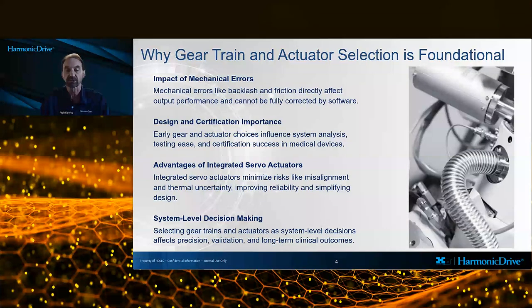Mechanical errors such as backlash, compliance, friction variation, and wear are transmitted directly to the output and cannot be fully eliminated in software. For example, backlash introduces dead zones and hysteresis that complicate force control and can destabilize impedance-based interaction with tissue in surgical robots.